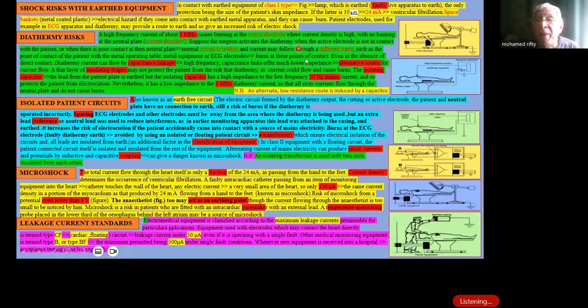Shock risk with earthed equipment, as we can notice before, that's the earthed equipment, which is the class 1 type. If there is a faulty affection of the lines entering the socket, as you can see, the earth is being broken, and then the patient is touching the stem of a lamp, and this lamp is being earthed. So whenever there's a fault, the electricity must go out. So it goes through the patient and comes out through this earth, where it completes the circuit. So he's liable to be affected by this fault earthing wire.